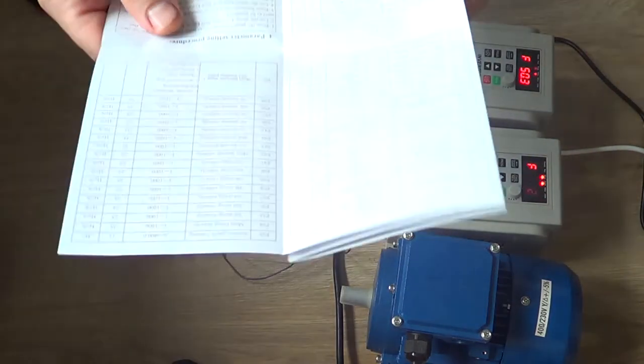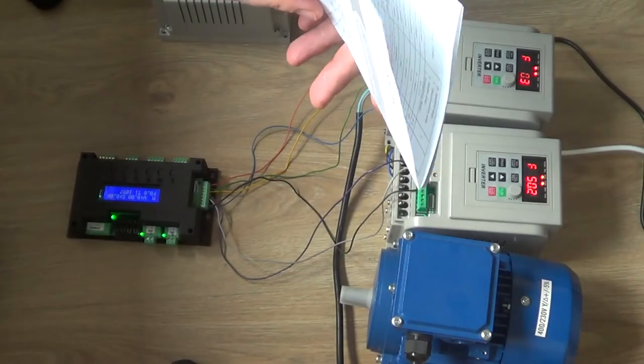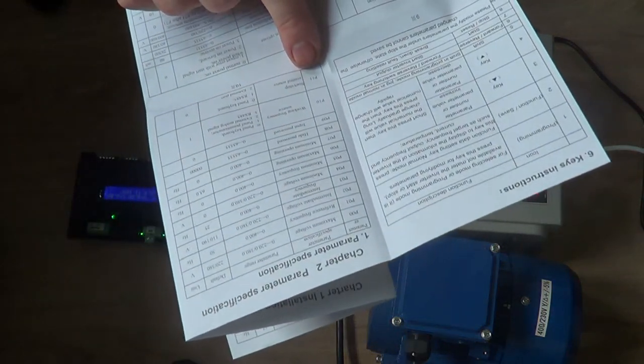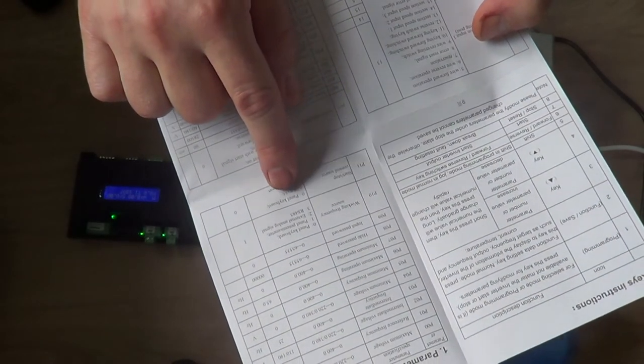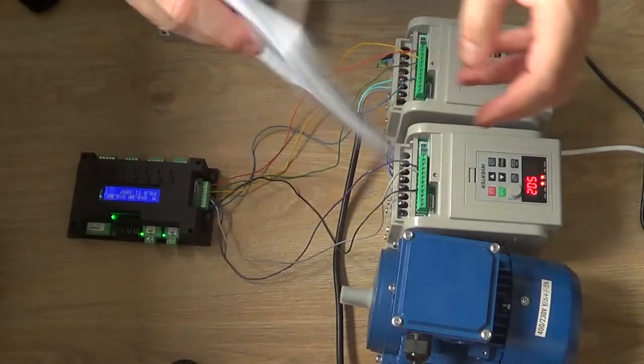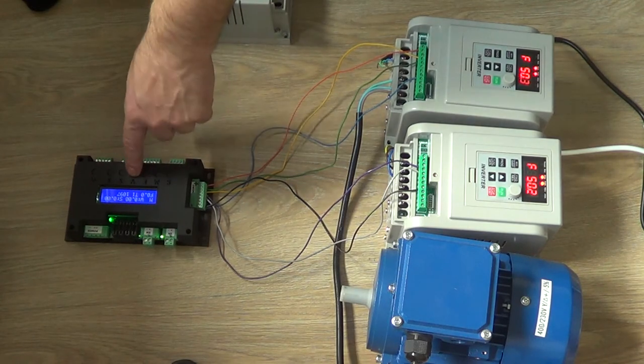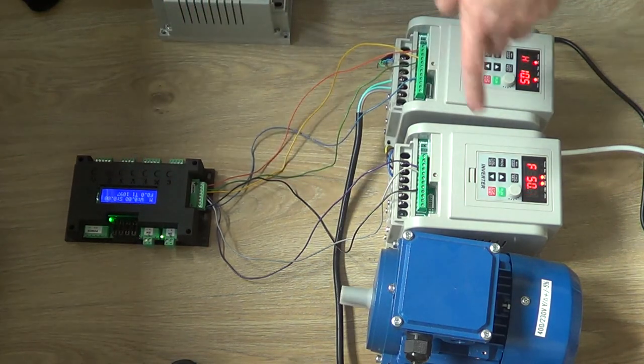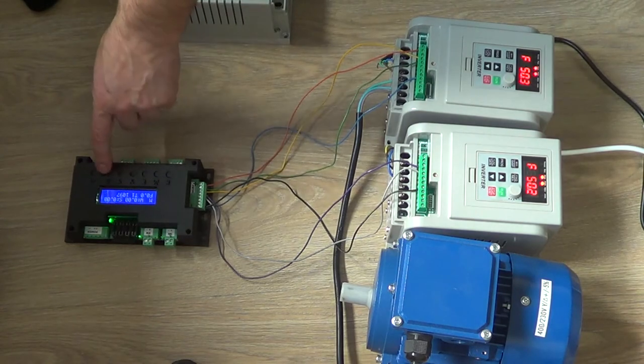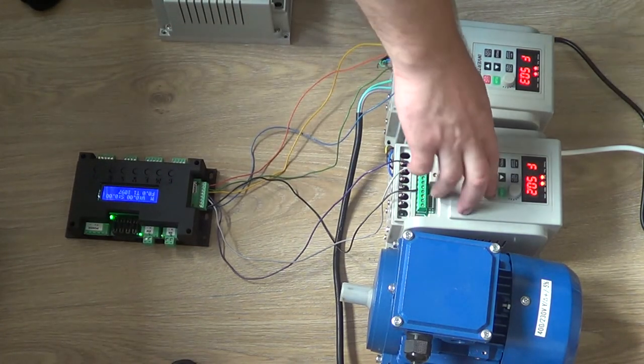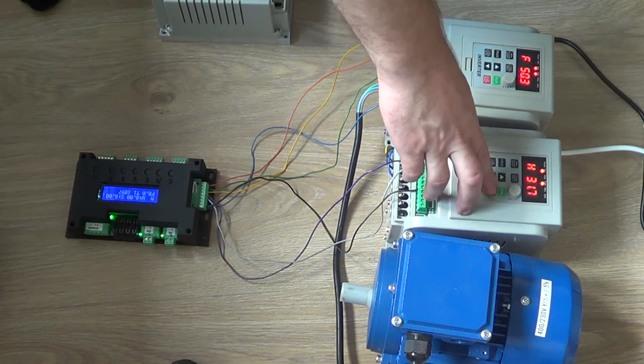What we're gonna change in the configuration is just parameter 11. We're gonna just put there 2 instead of 0. In one of the inverters I have it just made so that's why it's reacting from my push button. In that one the configuration is not done right now, so it can be just run by the switches, run and stop.